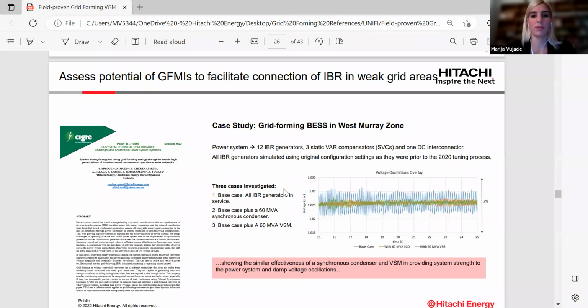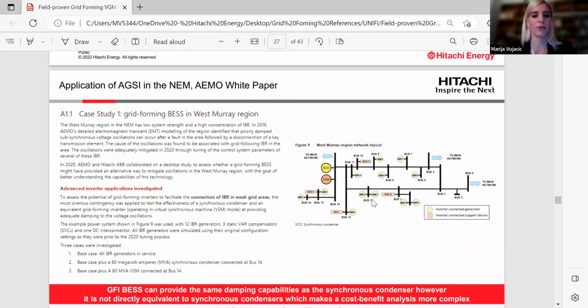But the main purpose of the paper was also to explore an alternative technology, and in this case a 60 MVA virtual synchronous machine was integrated, and the synchronous condenser was replaced by such a system. In terms of providing system strength to the power system and damping voltage oscillation, it was proven that the synchronous condenser and the VSM battery energy storage system have the same capabilities. Of course, these two technologies are not directly equivalent, which makes a cost-benefit analysis more complex. This is another paper published in collaboration with AEMO, and if you are interested, you can look into the results.